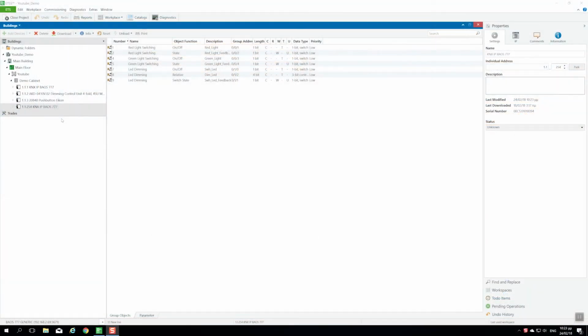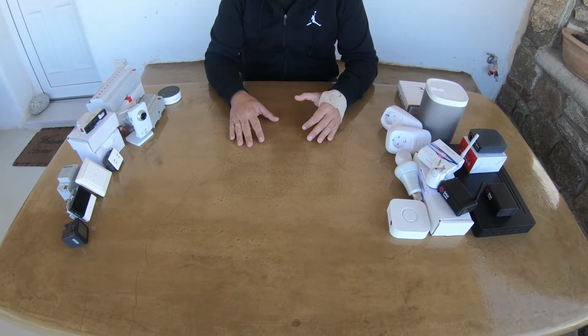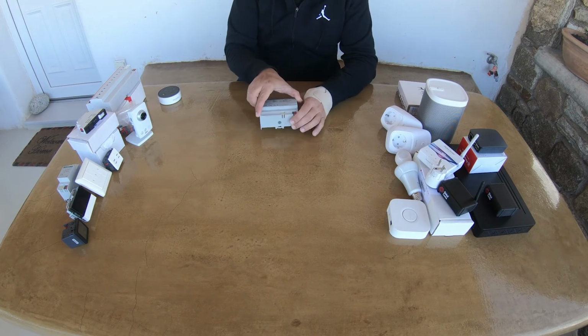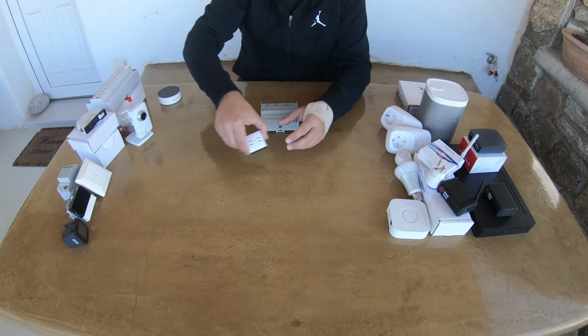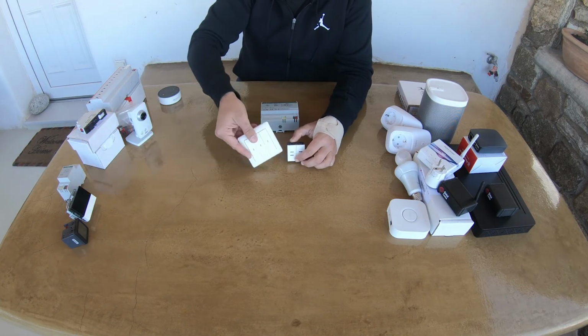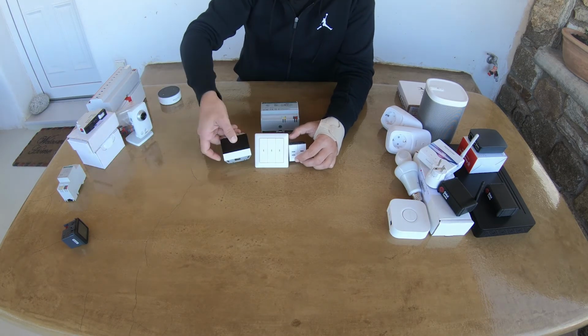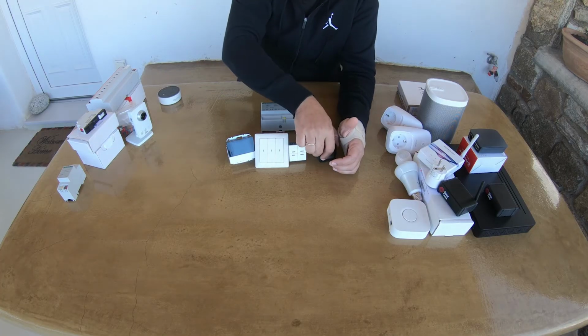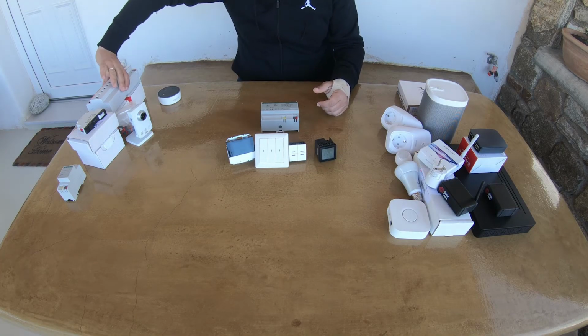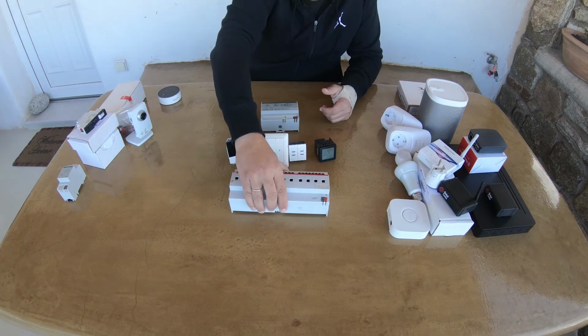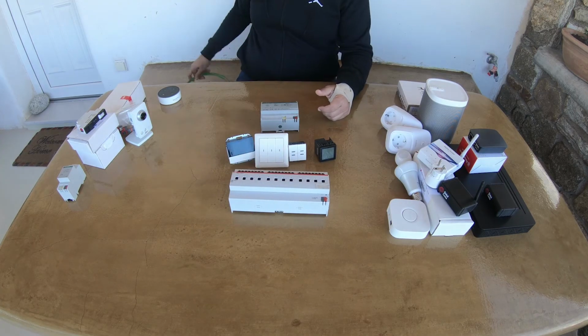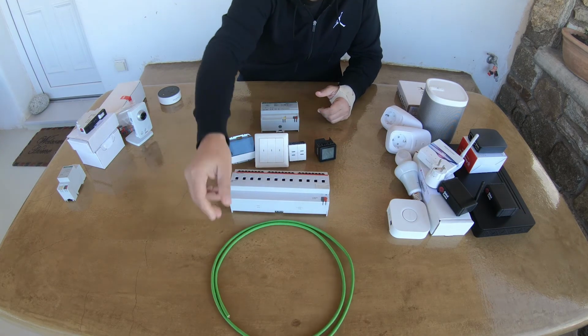All bus devices can be programmed with ETS software. A KNX system requires the following components: power supply for the power of the installation; sensors, push buttons, thermostats, brightness sensors, etc., that generate commands as telegrams; actuators, switch relays for lights, blinds, etc., that receive the telegrams and perform certain actions; and the bus that connects all sensors and actuators.